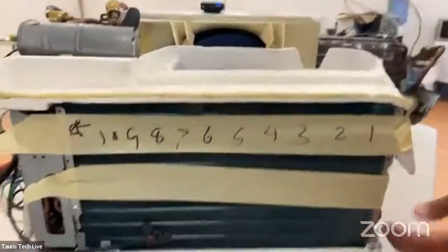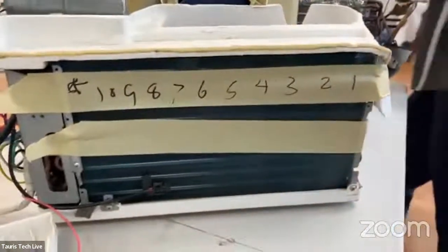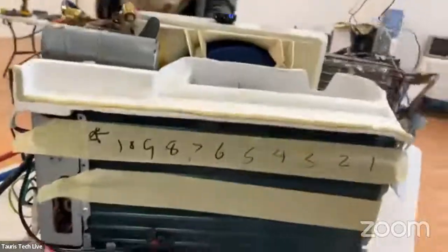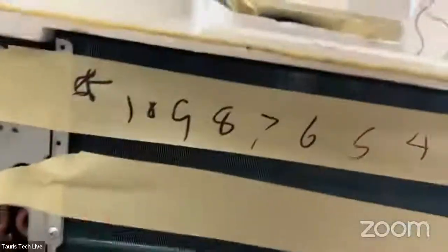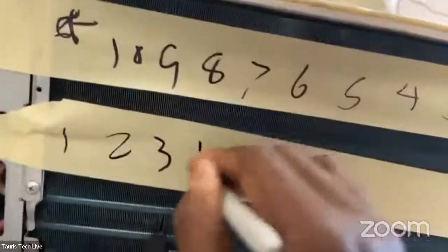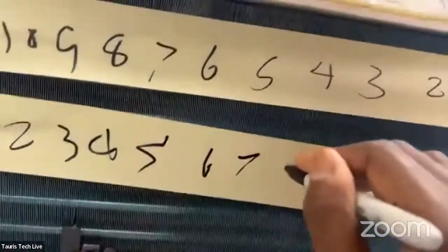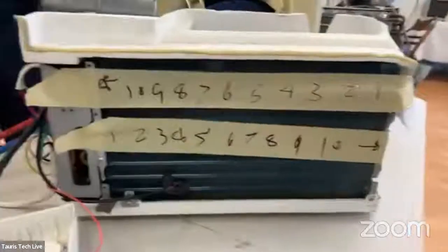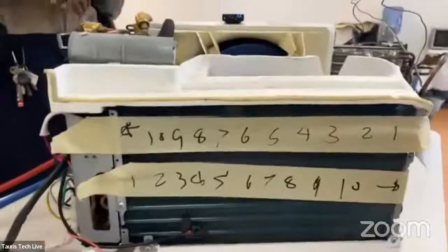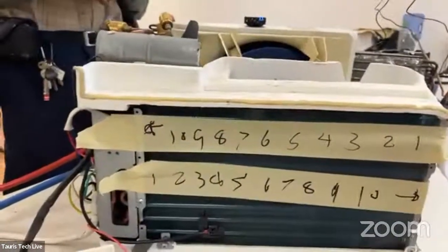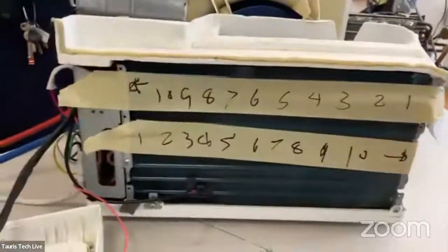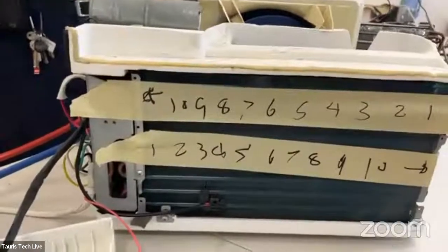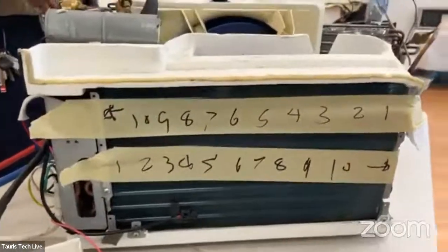Okay, now let's say I starve the evaporator and there is less liquid going into the evaporator, right? So if I have a coil, I'm going this way, that way, this way, right? So now I got 1, 2, 3, 4, 5, 6, 7, 8, 9, 10. If I starve the evaporator, my superheat is going to what? It's going to increase, because now more of the coil is being used to absorb superheat, which is what type of heat? Sensible heat, which is heat you can measure with a thermometer.